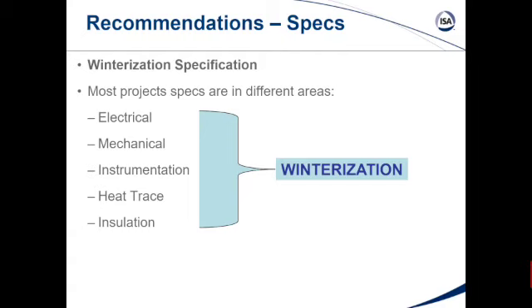And that's through control and monitoring. I'd say a large majority of plants, when you look at their winterization systems, have majority freeze protection - it's not process maintain, it's just we don't care what the temperature is, we just don't want it to freeze, which is fine. So what they're almost always doing is putting in group controlled panels - basically just a power distribution panel with a main contactor that interfaces with a single mechanical thermostat sensing ambient air. The mechanical thermostat senses it's getting to 40 degrees Fahrenheit or cooler, slams that contactor shut, and turns on all your heat trace. That's typically how things are controlled at these power plants.